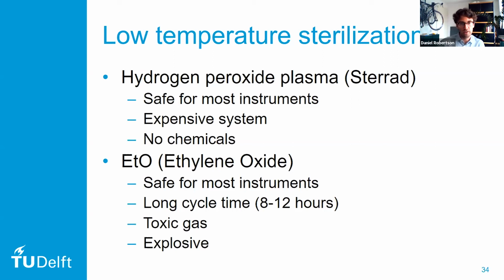The other common one is ETO, or ethylene oxide, which is also safe for most instruments, but it has a very long cycle time. Now, ETO is a very toxic gas. It's a suspected carcinogen, and it's explosive. And the reason why the cycle time is so long, 8 to 12 hours, is that that's the time that's required for the gas to safely disperse.